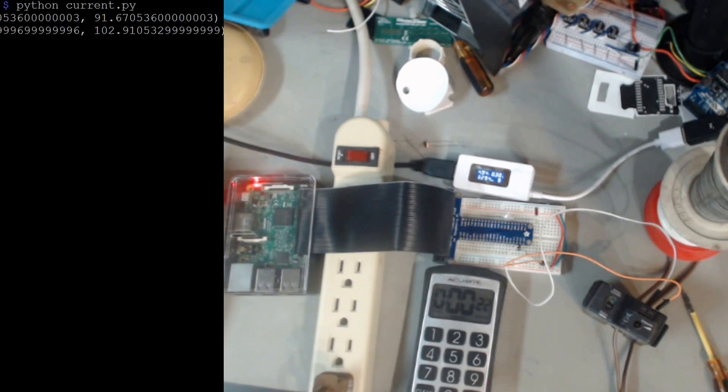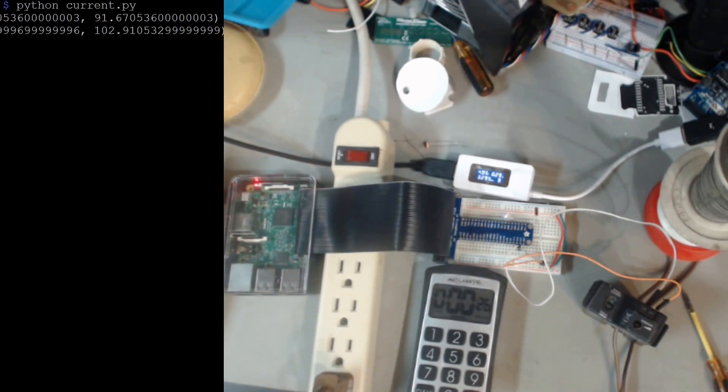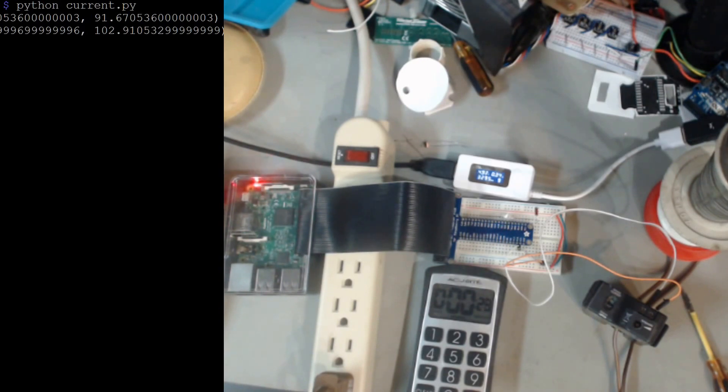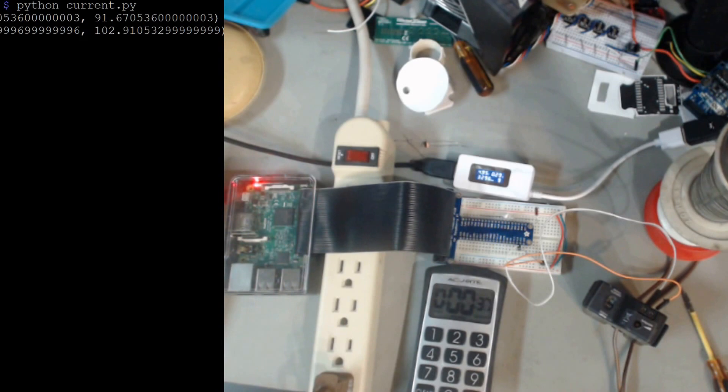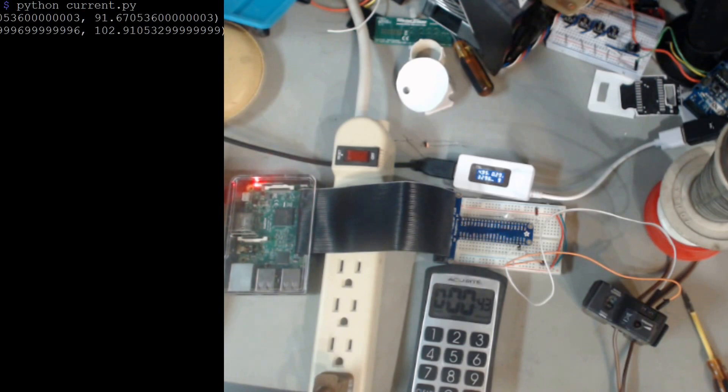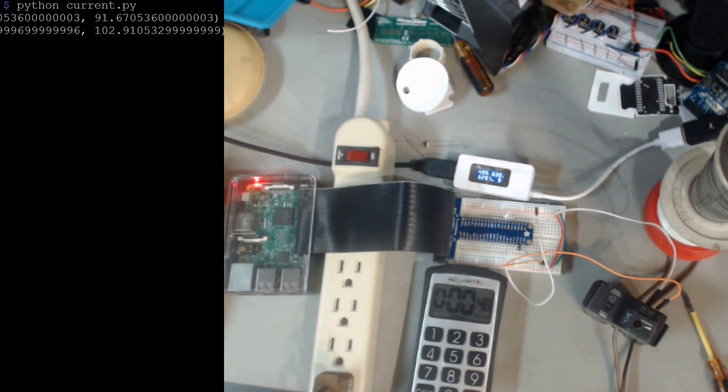So if you were to monitor a hot water heater, water pump, furnace motor, or whatever it is that you want to keep track of the duty cycle, if you know the power consumption for those devices when they're on, then you can just multiply the number of seconds on by the power per second. And you can get daily usage. You can find when the peaks are and all of that kind of stuff with just a digital input.